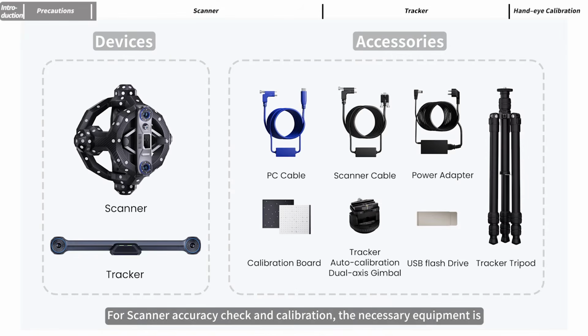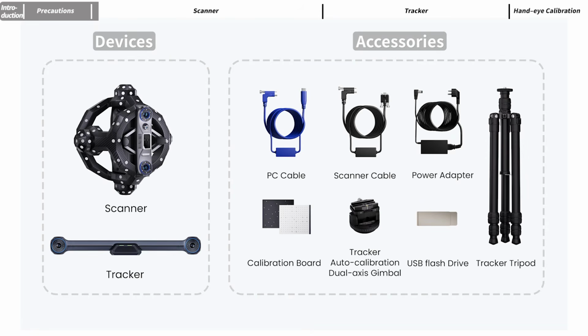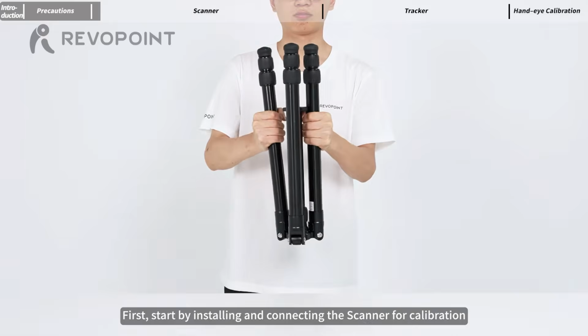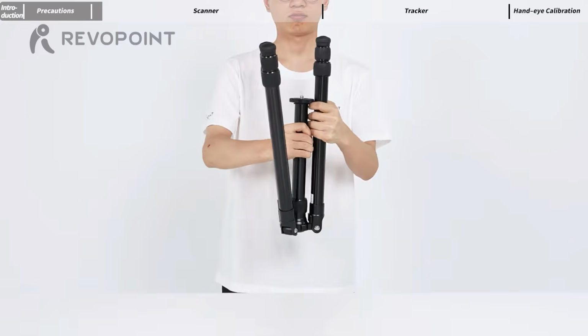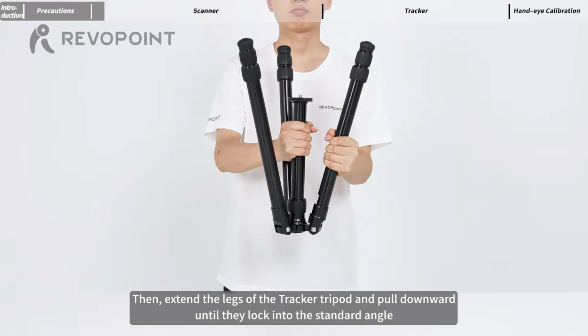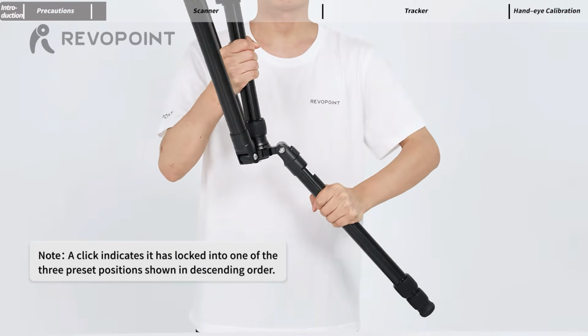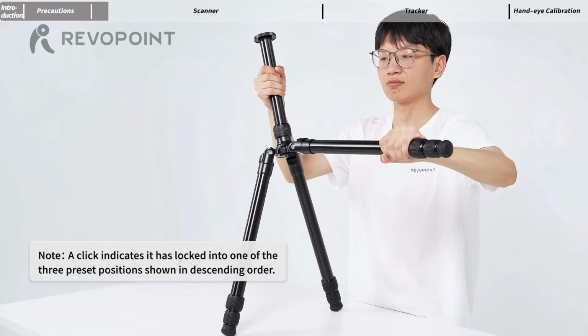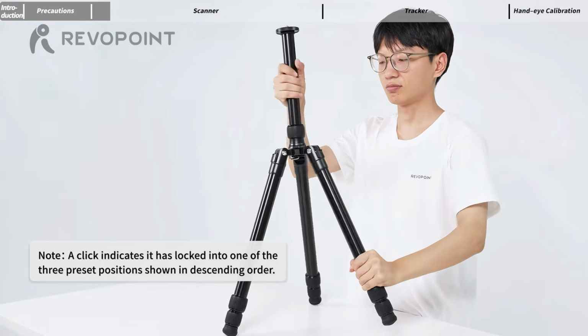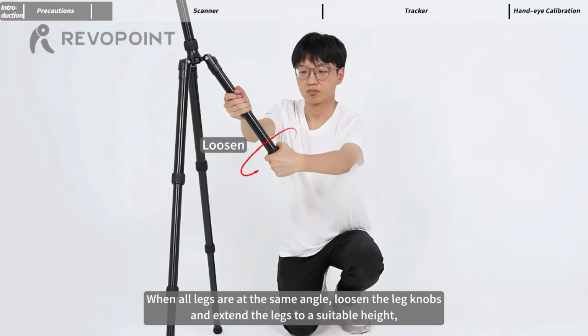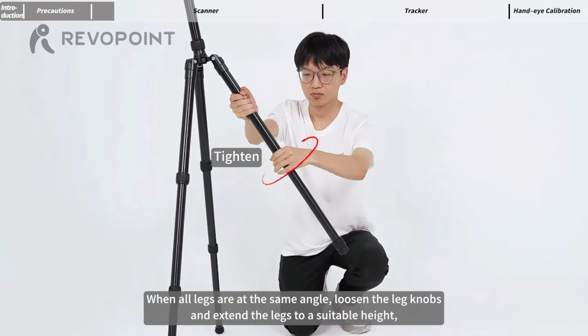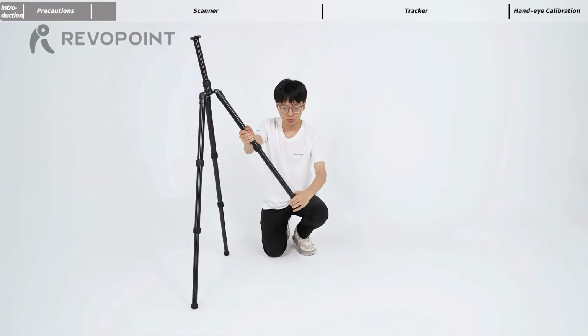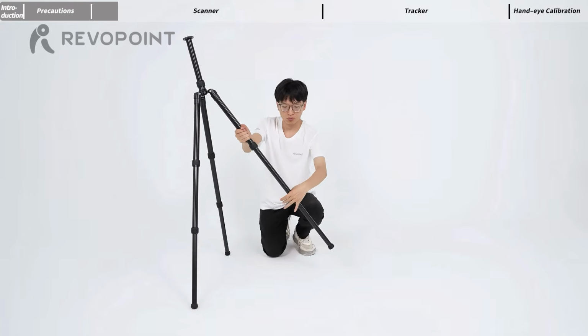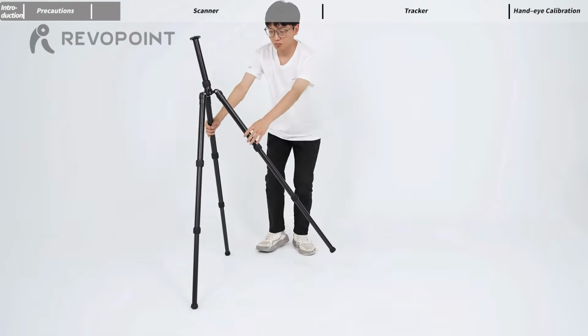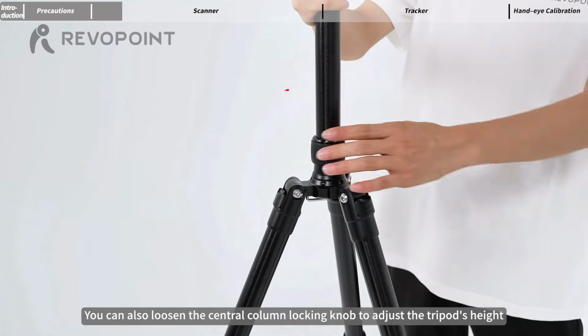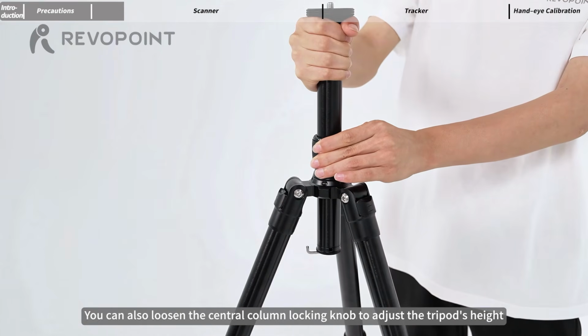For scanner accuracy check and calibration, the necessary equipment is: first, start by installing and connecting the scanner for calibration. Then, extend the legs of the tracker tripod and pull downward until they lock into the standard angle. When all legs are at the same angle, loosen the leg knobs and extend the legs to a suitable height, then tighten the leg knobs. You can also loosen the central column locking knob to adjust the tripod's height.